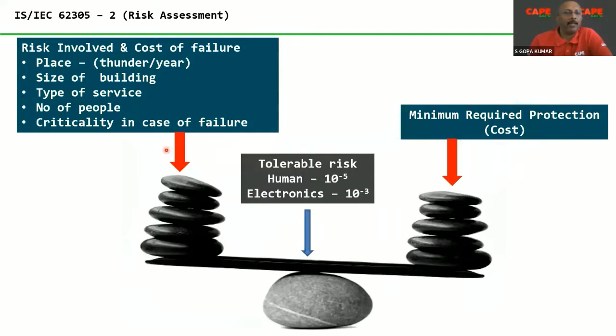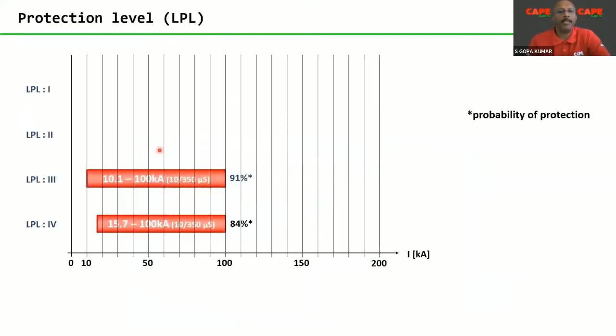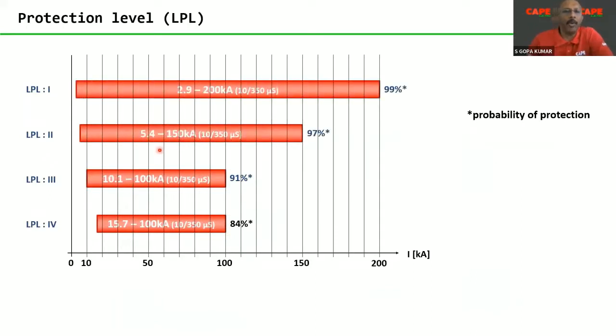Now, please understand that risk assessment for a larger area, a larger village, town, district, is not possible. Why I mention this is that there are some articles we are reading nowadays. People claim that village level lightning risk assessment has to be made, district level lightning risk assessment has to be made. All these are actually not possible. Risk assessment is made for a typical structure or a typical building, just to find out whether lightning protection is necessary or not. If necessary, lightning protection is classified into 4 levels.